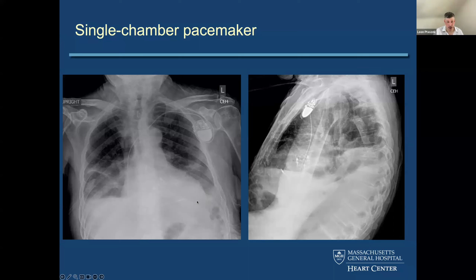As you very well know, the basic pacing system is comprised of 4 basic parts. There's the pulse generator, which contains the computing system and the system for pacing and sensing, as well as the battery. And then there's the leads, which attach the pulse generator to the heart. In this case, I'm showing you a dual chamber system, knowing full well that the number of leads per system will vary from 1 to 3.